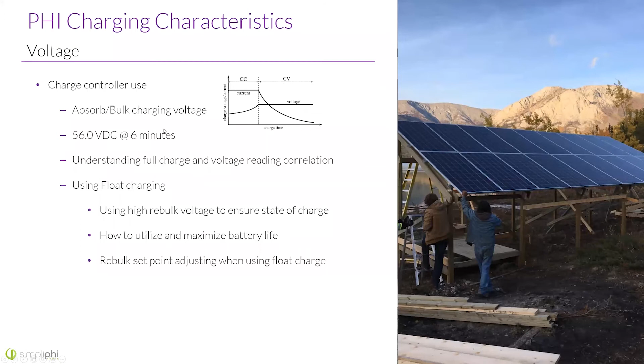But our manuals are going to be updated soon. We're just going to say 56 volts at 6 minutes, regardless of the charging source. That is going to be the standard from now on. This 54.4 at 1 hour, the only reason you should ever use that is if you've got an older charge controller or charger that does not go down to 6 minutes on the absorb time.